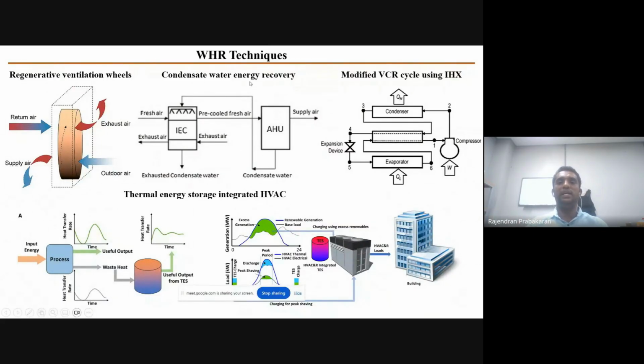And the second category, condensate water recovery. Usually the condensate water temperature might be around 10 to 15 degrees Celsius, almost equal to the dew point temperature of the air. The amount of water produced is around 15% of the total cooling load of the unit. So if we recover this condensate water, we can pre-cool the air again, or if it is a big capacity system, we can use the condensate recovery for cooling a small room in the same building. Additionally, this condensate water can be used for irrigation purposes also.